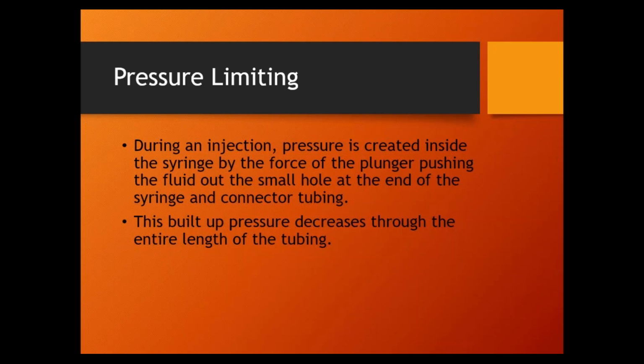1,200 pounds per square inch. Yeah, and so think about that. Is that really for the patient? I mean, you're biomeds. You guys work on infusion pumps, right? What's the occlusion pressure on an infusion pump? Maybe know off the top of your head, roughly. 6 PSI, 8 PSI, 10, you know? I mean, when an infusion pump hits 8 PSI, shut it down, stop, whoa, wait, what are you doing, dude? You're gonna kill the guy.